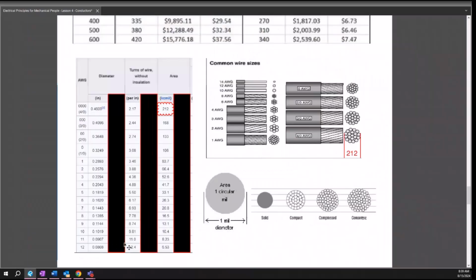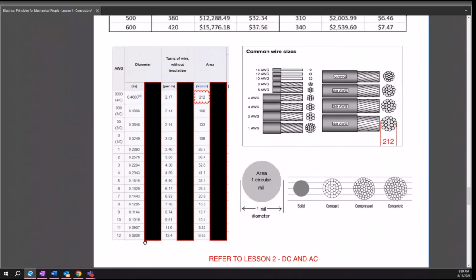So for instance, let's go to number 12—it is 6.5 KC mil. Instead of saying 'I need a 6.5 KC mil conductor,' I just say I need a number 12 conductor. So all the way up to 4/0—this is a number 12, a number 10. We don't really use number 11. Number 12, 10, 8, 6.